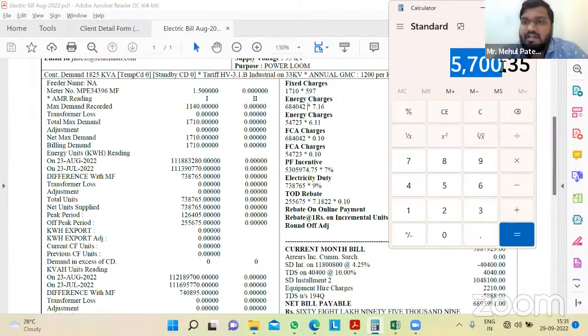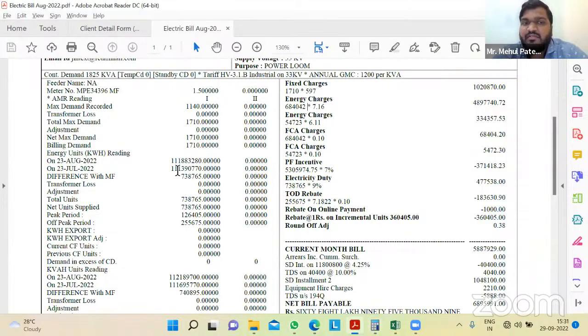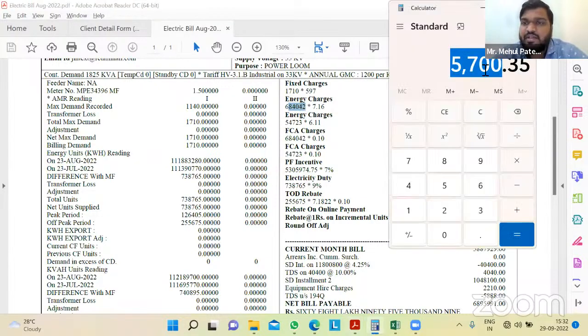I hope this is clear, how to figure out the total PV capacity, that is the power capacity of the solar power plant. For this particular customer whose consumption is approximately 6,84,000 units per month, which came down to 22,000 units per day, we finalized 5.7 megawatt as the total capacity of the solar power. I hope this is clear till now.